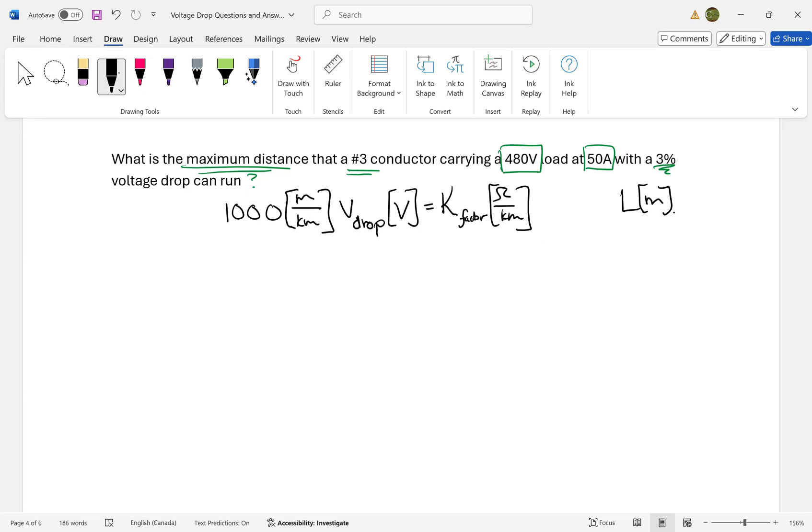To find the maximum distance, we solve for length L. Length is the distance in meters and will be less than or equal to the calculated value. Solving for L means rearranging the equation. The equation isolated for length is: L ≤ (1000 × Vdrop) / (K × F × I).